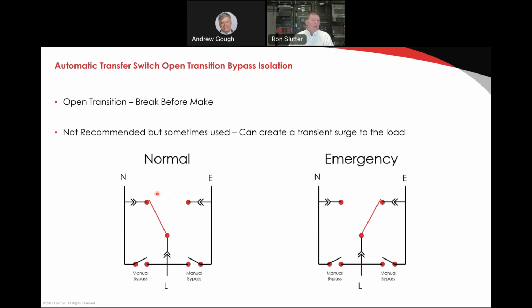There is maintenance required for an ATS. If you're not maintaining your ATSs, you will eventually run into a problem. Significant issues with grease drying up over years of service will lead to linkage hanging up within the ATS. And that's not a good thing. That will cause you to have to deal with the ATS. So this gives you the ability to maintain an ATS while it's in the midst of providing power to the load. And you can see, other than that, it's the same as a standard ATS. This is open transition, so it's going to move from the normal side to the emergency side and back and forth with no delay.